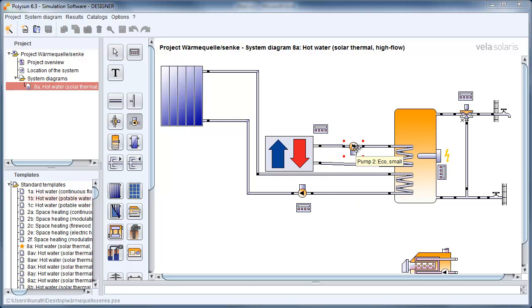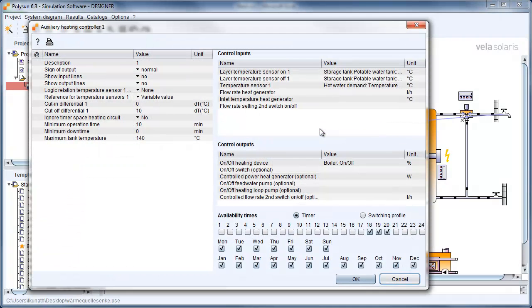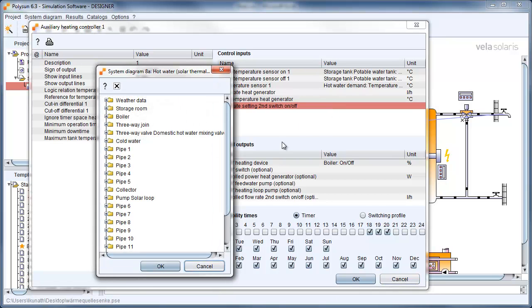I recommend not to delete the gas burner immediately. It is easier to change the controller settings first. To change the controller settings, double click on the auxiliary heating controller and define the design flow rate for the heat source.